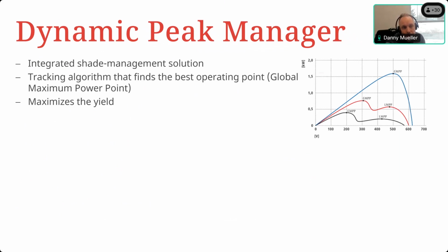If the same thing were to happen with a string inverter—let's say, for example, Power One was a company around 8 years ago that made string inverters, and now that inverter is failing—what you can do is choose pretty much any string inverter out there, Fronius or others we carry, and replace it very easily because string lengths are the same. Yes, you lose warranty on that product, and the customer has to pay for a new unit. However, you don't have to go on the roof and restring anything or take off any solar panels. So from a longevity perspective, it's a much cleaner solution and a lot more peace of mind.